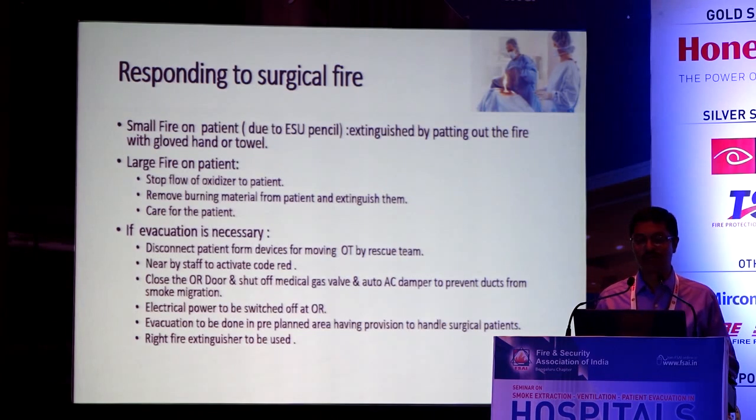Care for the patient. Then if evacuation is needed, disconnect the patient from the devices, because so many devices are connected. You have the syringe pump, infusion pump, and anesthesia ventilator connected, and you have the plate for the electrosurgical unit. You have to disengage those things. Then only you can take out the OR table.